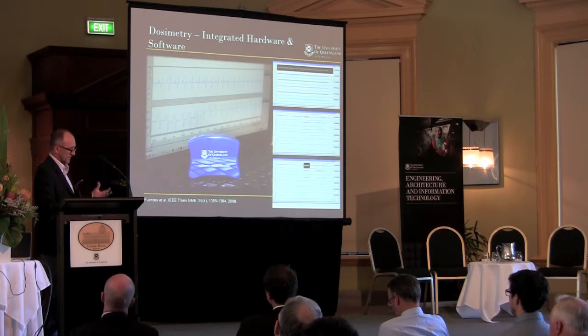So anyone who walks past a static magnetic field, or who is exposed to a static magnetic field that is changing even slowly, will have current induced in their body because we're really an agglomeration of conductors. And this was a regulatory limit set to that. But it turned out that the limit was such that no one could ever have an MRI scan. No one could work around aluminium smelters.